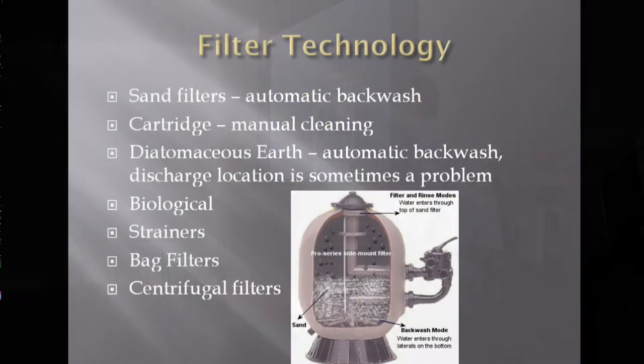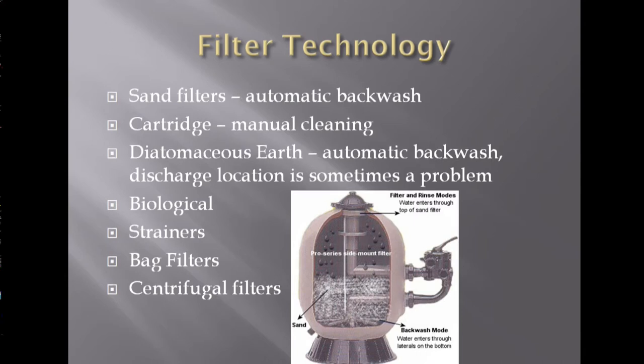Filtration. There are different products out there, or different methods or media for filtration. We use a lot of sand for commercial projects. I like it because I can automate the backwash. You can clean the filter without having to take anything apart. In fact, I can do it electronically from an iPad if I wanted to, by just putting a motor actuator on the backwash valve.